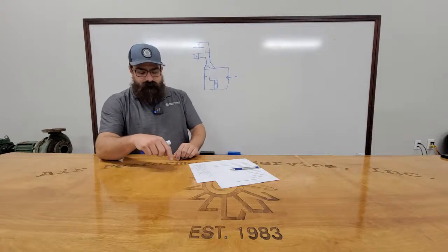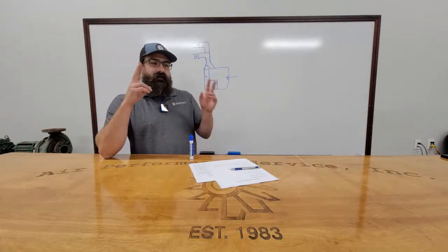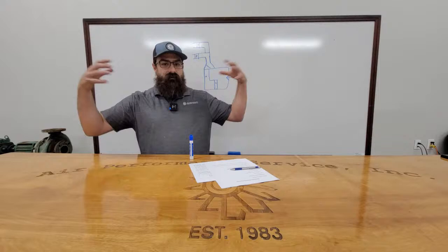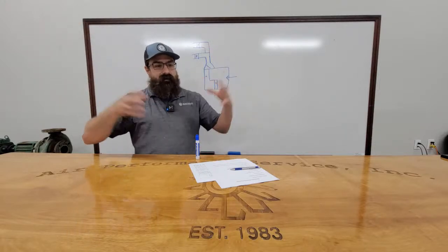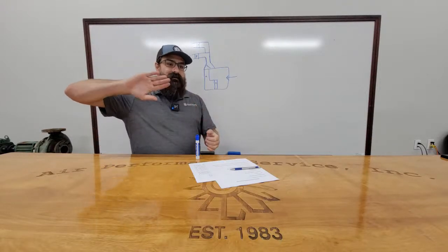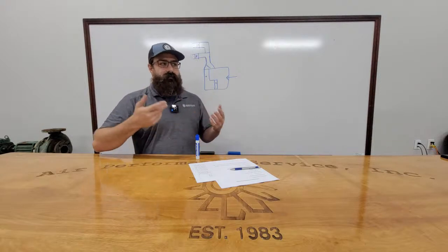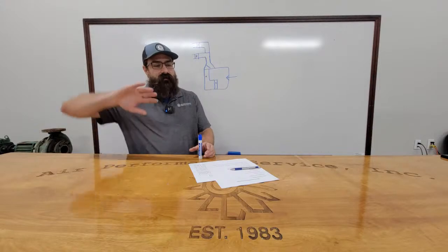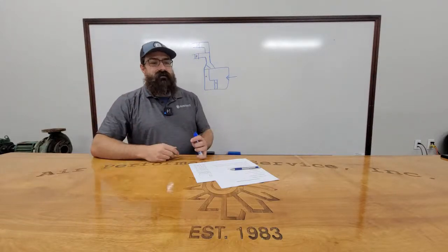So it's doing return air CO2, because their return is technically mixed, because the VAV is constantly pumping air into the room, which is pulling from the return. So it's got 3000 CFM of outside air plus the return mixing together coming into the return inlet of the unit. That outside air will modulate closed down to 1200 CFM if the CO2 is below 900 parts per million. If it gets close to or above 900 parts per million, it'll start to ratchet its outside air up to drop that concentration of CO2.